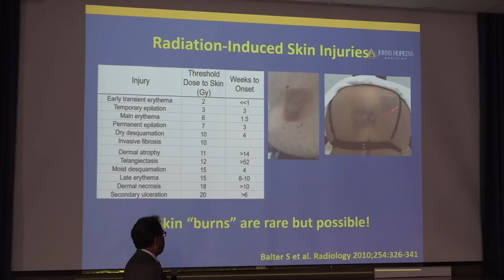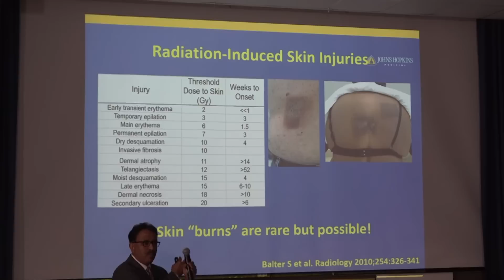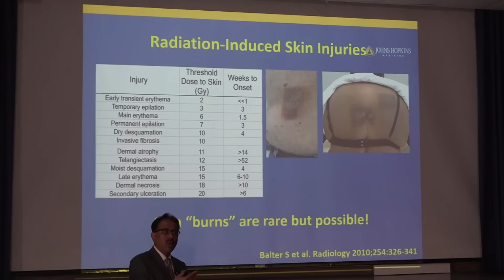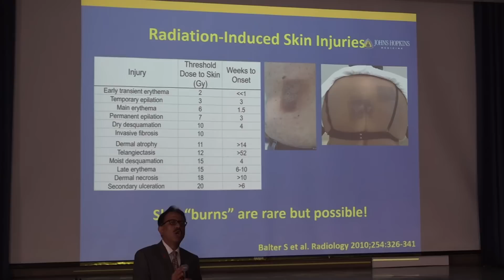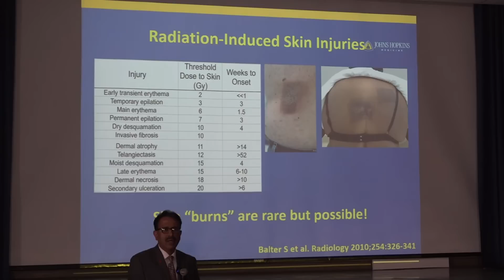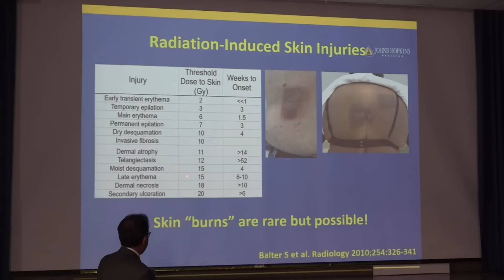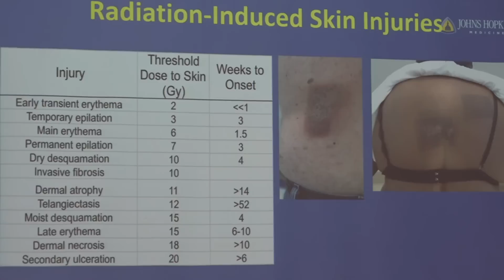This patient, as you can see the direction here, underwent a cardiovascular procedure. The shape of the injury tells you it is a biplane system positioned in opposite ways, and the obesity factor also plays a part, because the larger the patient, the more exposure is needed to penetrate, so the system automatically produces more radiation to produce the same image quality. This resulted in this type of injury, which can be almost equal to 15 gray. 15 gray is a very large dose. To put it in perspective, we typically talk about milligray, 1, 2 or 3 milligray. If somebody gets 15,000 milligray or 15 gray, that's almost like a therapeutic dose, and that's a permanent injury. So just to give an example, skin burns are very rare but possible.